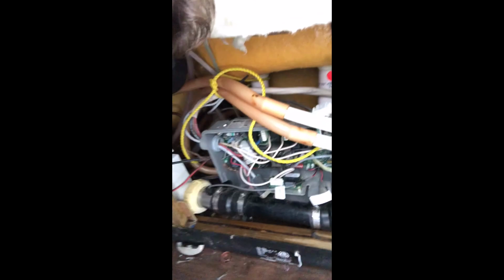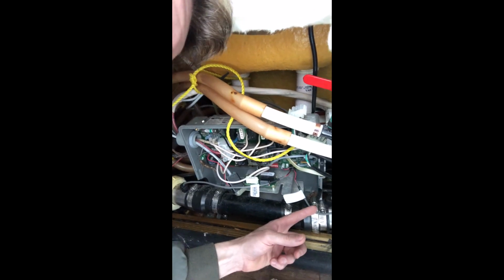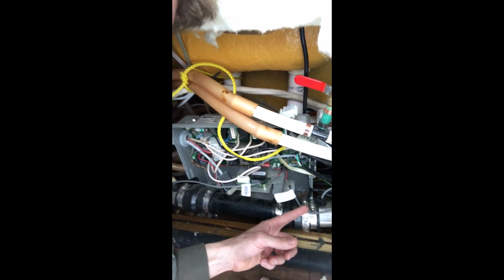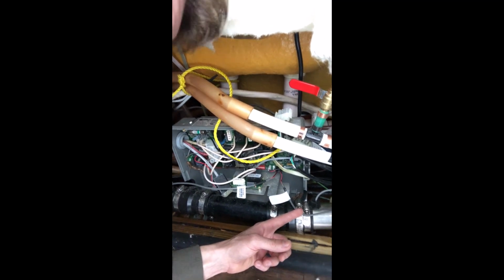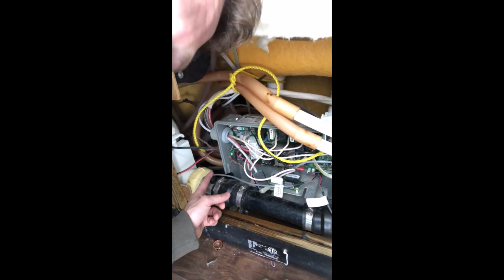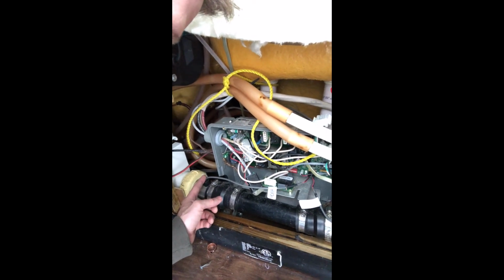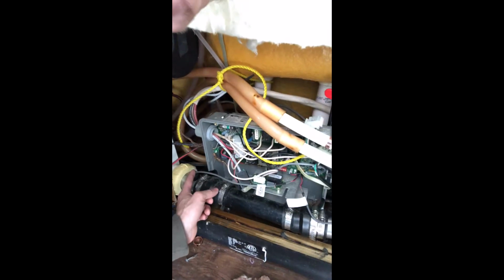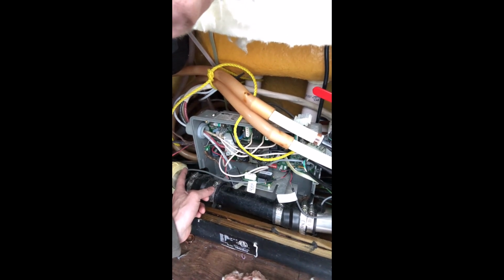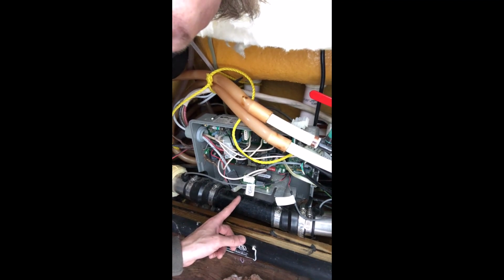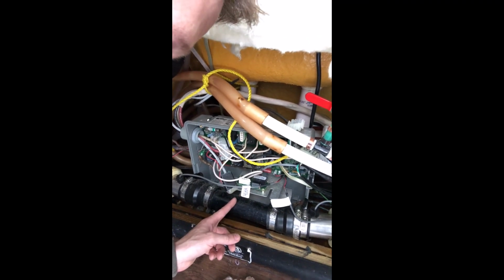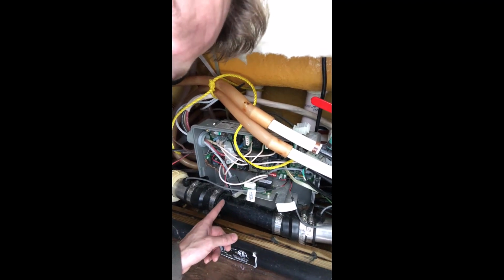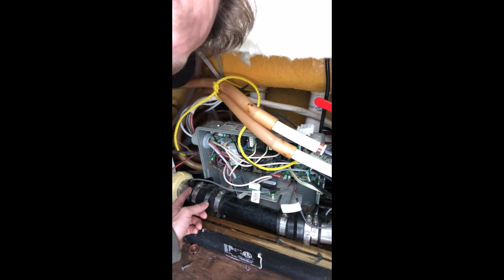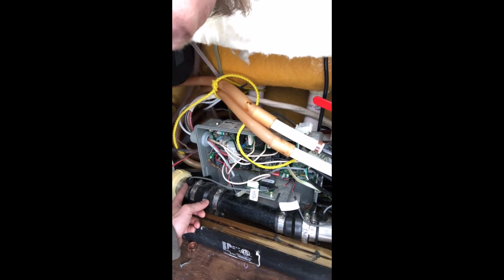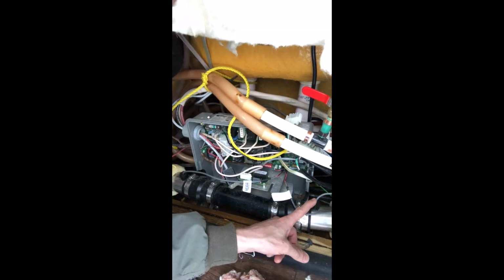But unfortunately we got some issues right now with these heating sensors. There's a heating sensor upstream of the now missing heating element, and a temperature sensor downstream of the non-existent heating element. What these things do is tell the computer that there's a call for heat, and the element turns on and the water's flowing this way, and when the water reaches this downstream temperature sensor, it's reading hot water, whereas the upstream sensor is saying I still got cold water coming in here, so everything's working like it should.